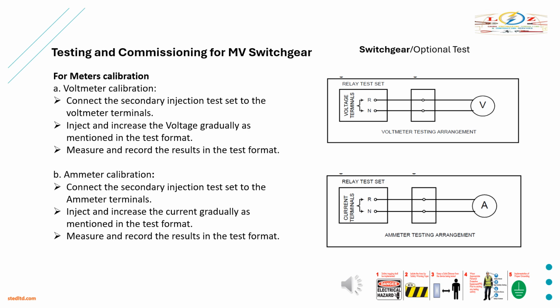For ammeter calibration, connect the secondary injection test set to the ammeter terminals. Inject and increase the current gradually. 1. From 0 to 25%, 50%, 75% and 100% of the full-scale current of the ammeter. 2. Record the corresponding ammeter readings. 3. Inject 100% of the normal current and record the corresponding ammeter reading on the test record sheet.